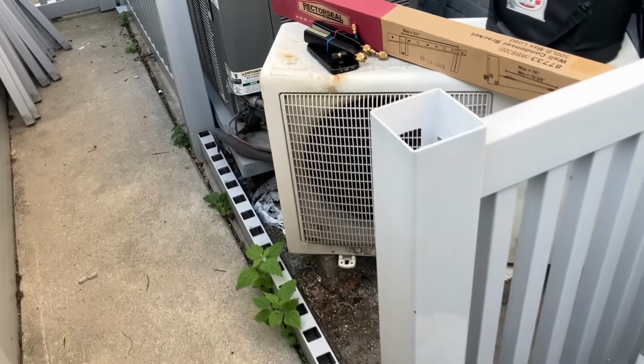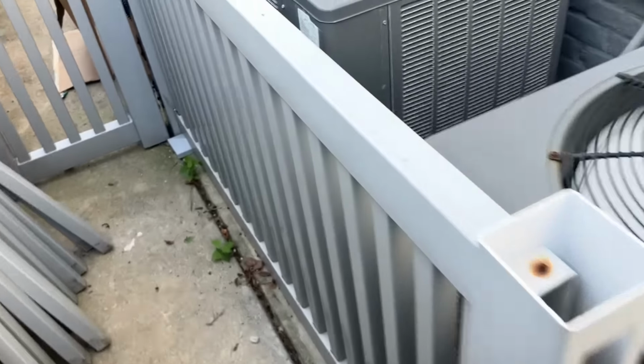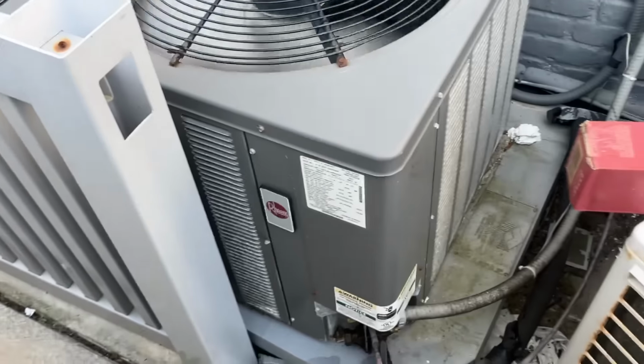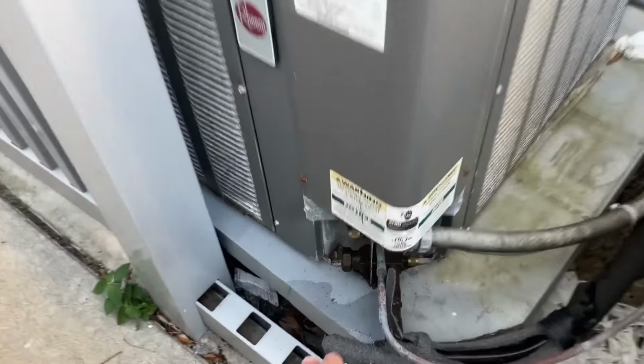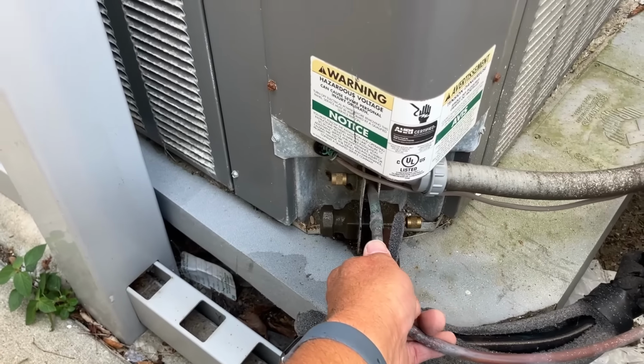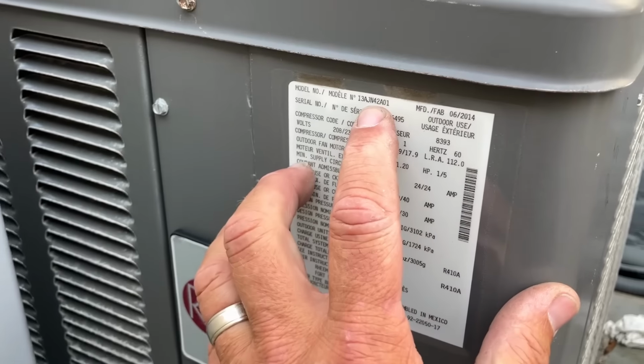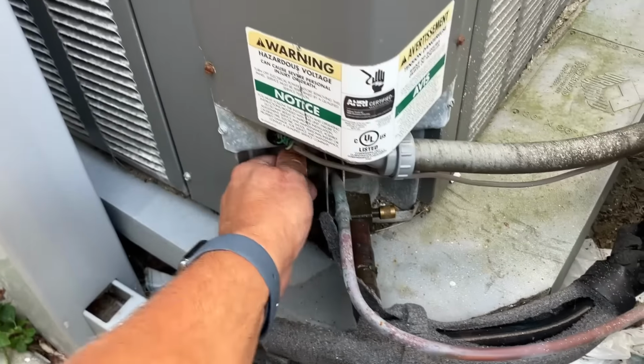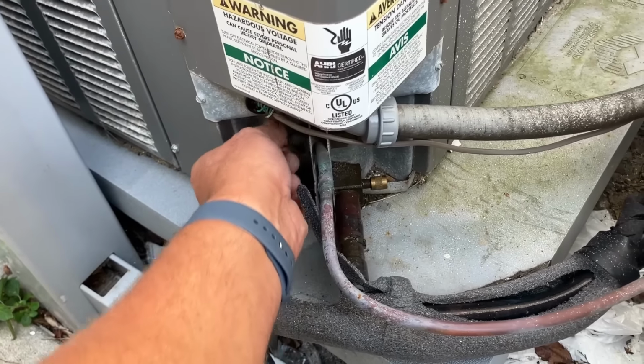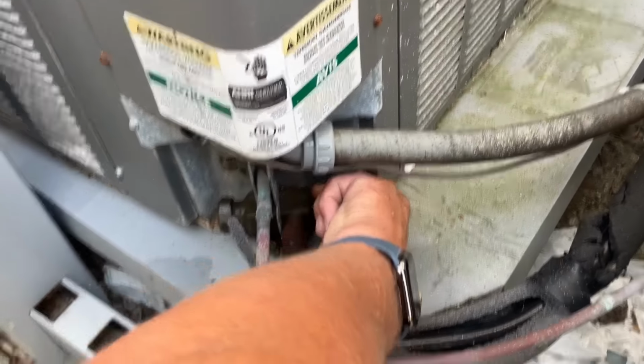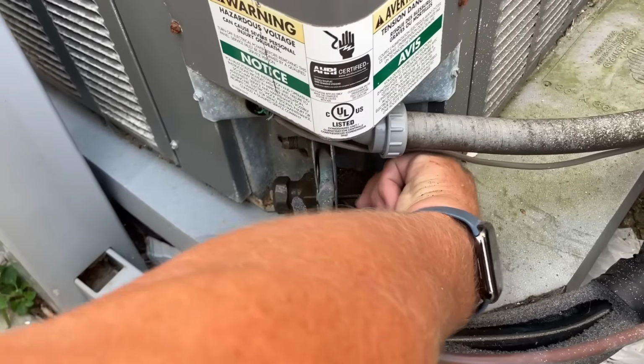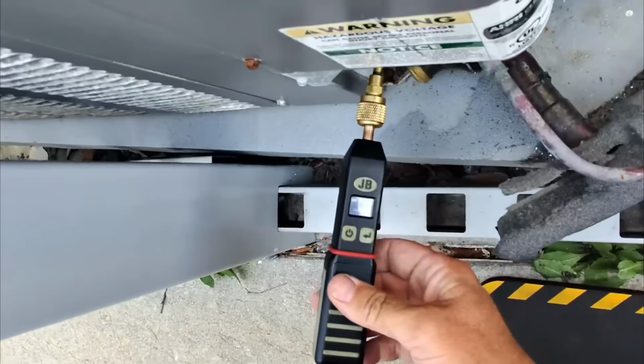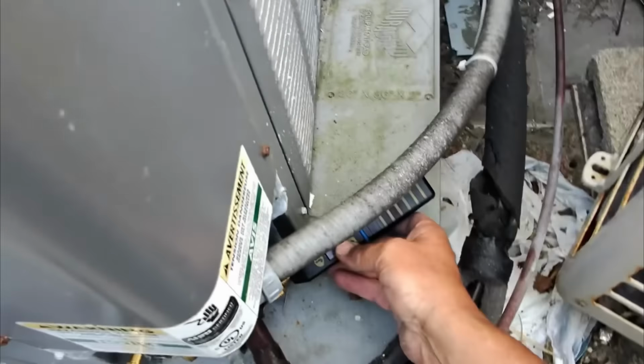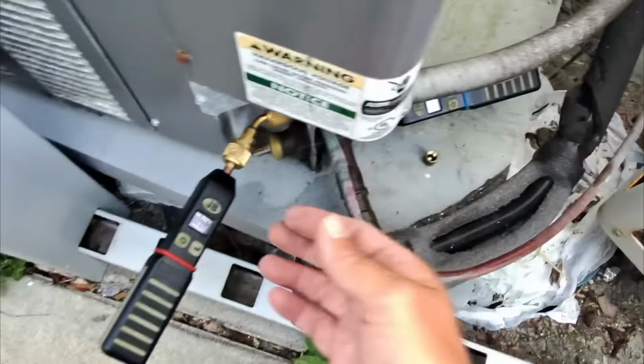All right, we're gonna start outside by pumping down the outdoor unit. Fortunately, I was able to dissect this PVC fencing that's directly in front of the line set connections at this 3.5 ton outdoor unit. Let's take these caps off, hook up our gauges, and pump the system down. See, -8 and almost -8.